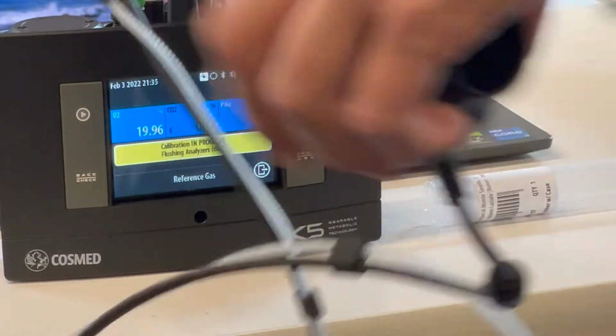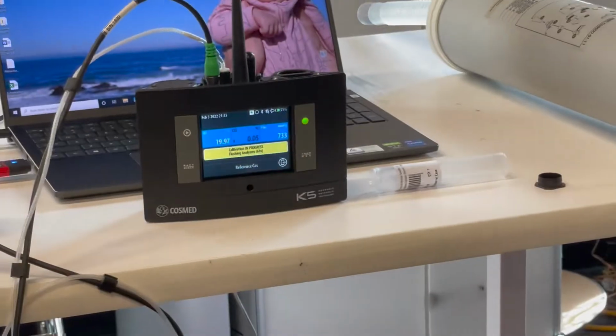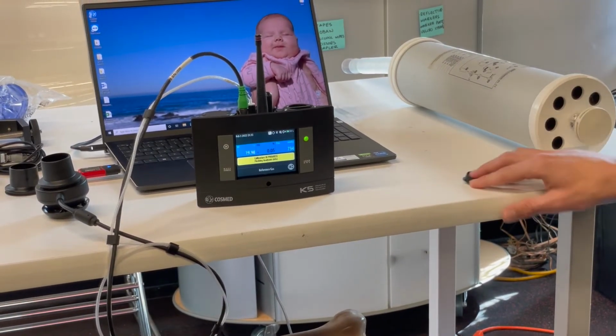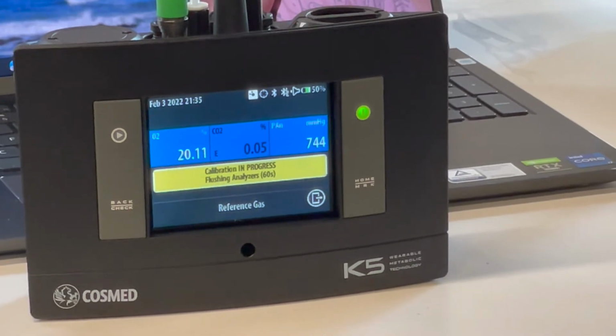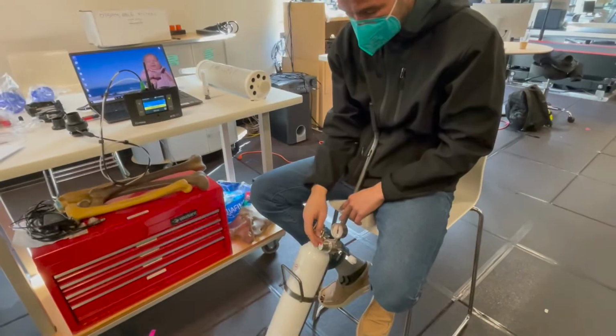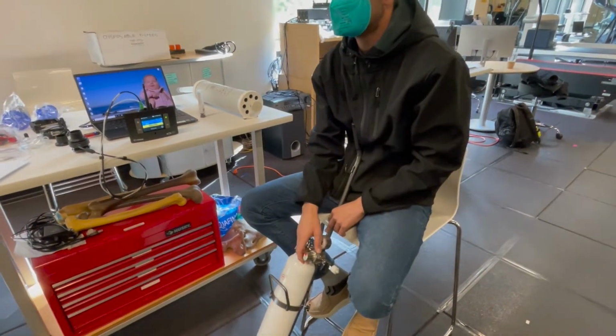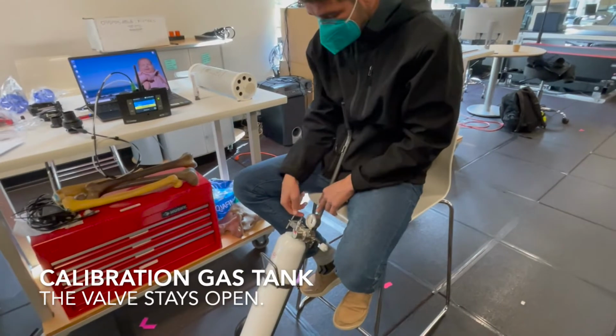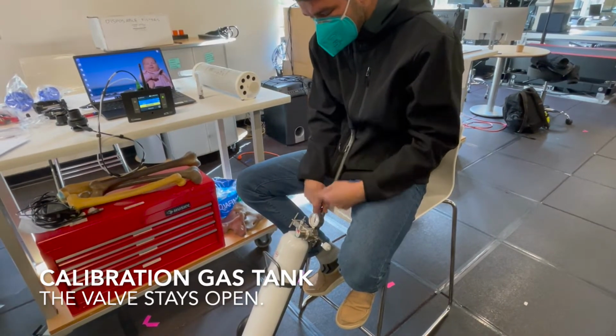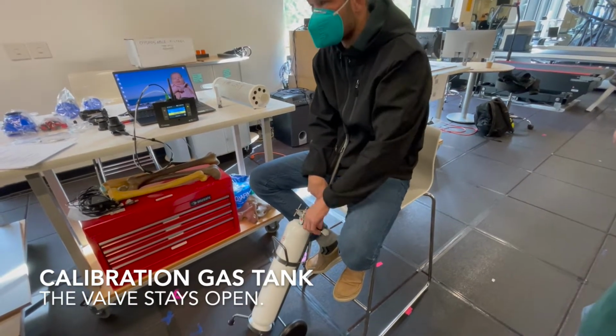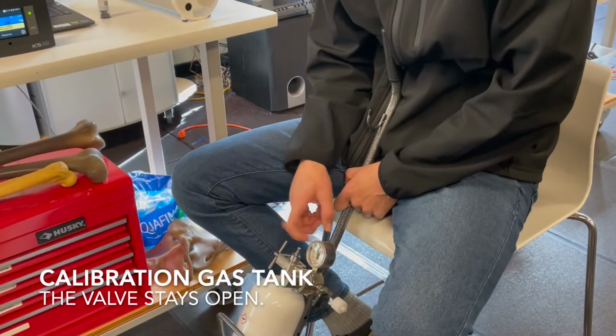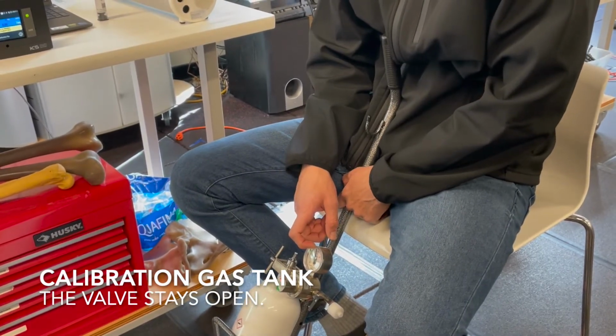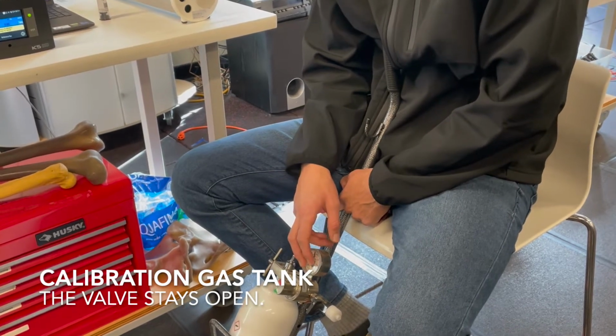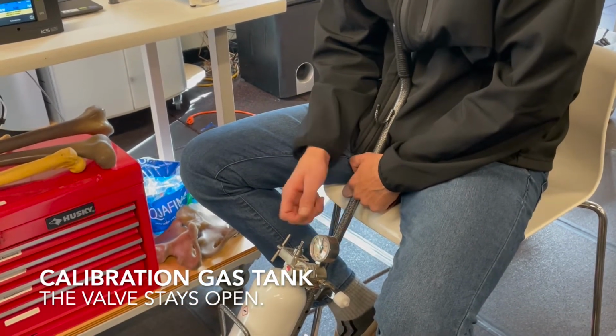It's first gonna have us just let this guy hang out so it can sample and flush the analyzers. So this is our gas tank. Very nice with the K5 because the regulator is set to only have one output pressure, so nothing ever needs to be adjusted. This valve is going to always stay open, and you just control the flow by turning this nozzle. And this is just telling us the total amount of pressure that's in the tank. They come standard with 2100 PSI. This guy has about 2000. It's pretty much full.